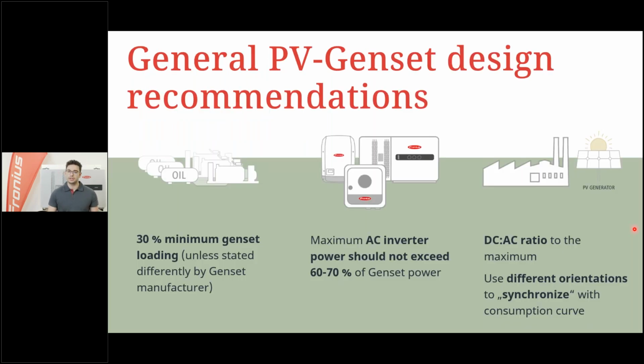All right, before we head on into a general overview of which inverters we have ready to use, I quickly want to point out 3 important recommendations when it comes to the design. The first one we have already heard: it's a minimum genset loading that we do not want to undershoot. For most of the generators, it's about 30% minimum genset loading. Some manufacturers point out something different. And there are also different kinds of generators out there. For example, a gas-driven generator tends to have a higher minimum loading of 50 or even 60%. And we need to focus on that. We must not forget that.